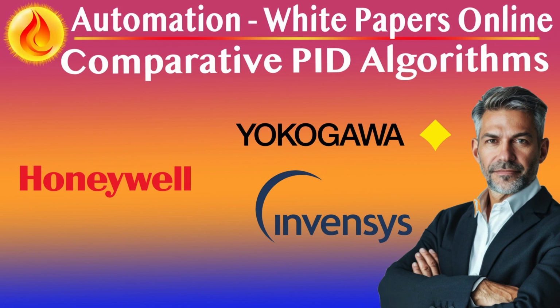In high-noise environments, e.g. flow control, steam pressure loops, this difference can significantly impact loop reliability and actuator wear. Yokogawa is stronger for noise-sensitive and derivative-heavy loops, offering precision filtering and D-logic configuration. Invensys can handle these loops with effort, but requires manual filtering, tuning, and caution with Series D interactions.